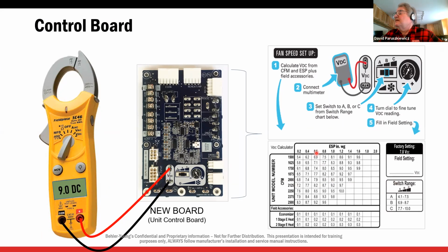Now, what happens if you say, well, I don't want to check the static, I'm just going to crank this thing up to 9 volts DC. And let's say you only have 0.4 inches of static. You can see that should only be 7. The higher that DC voltage is, the faster that blower motor runs. So if your static is only 0.4 inches and you set it at 9, you're going to be ramping that motor up too high, and you'll probably be tripping on overload. Okay, if I don't set the static high enough, I might not have enough airflow. All right, so this is not a step that we can bypass anymore. It's pretty simple, but you have to do it.